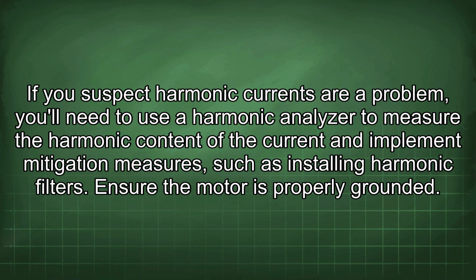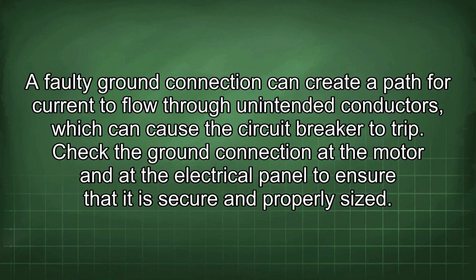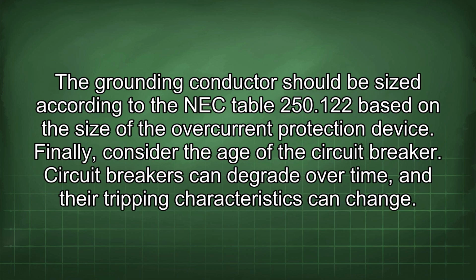Ensure the motor is properly grounded. A faulty ground connection can create a path for current to flow through unintended conductors, which can cause the circuit breaker to trip. Check the ground connection at the motor and at the electrical panel to ensure that it is secure and properly sized. The grounding conductor should be sized according to the NEC table 250.122 based on the size of the overcurrent protection device.